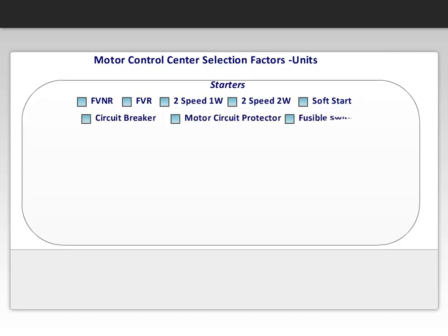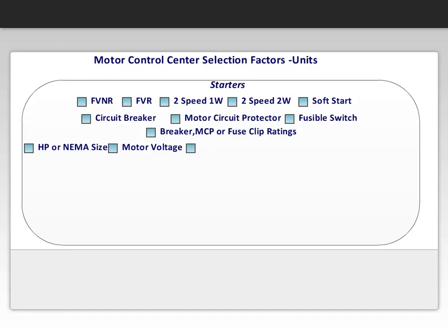Does he want a circuit breaker, motor circuit protector, or fusible switch? Once the type of disconnect is established, it's necessary to know the size of the trip or fuse clip that is required. We need to know the horsepower or the NEMA size, the motor voltage, the control voltage, and if the customer requires separate control or is going to control it by means of a control transformer inside the unit. We also need to know what options or modifications the customer wants.